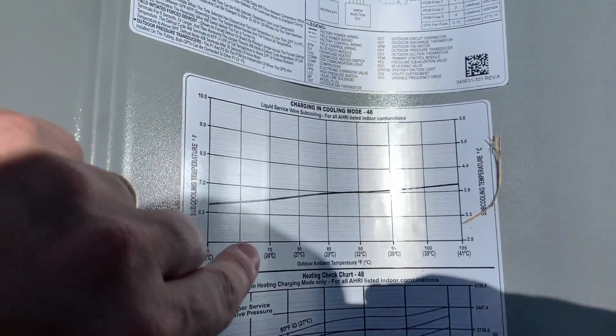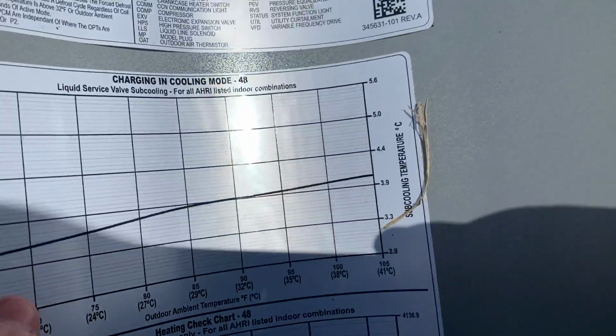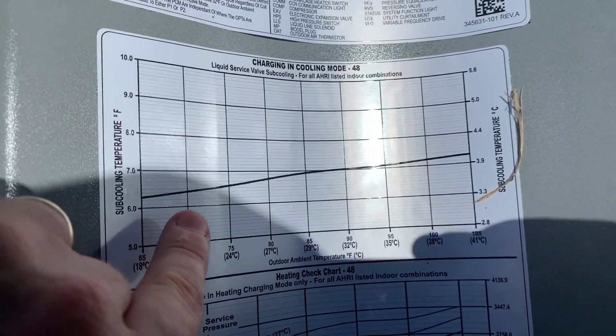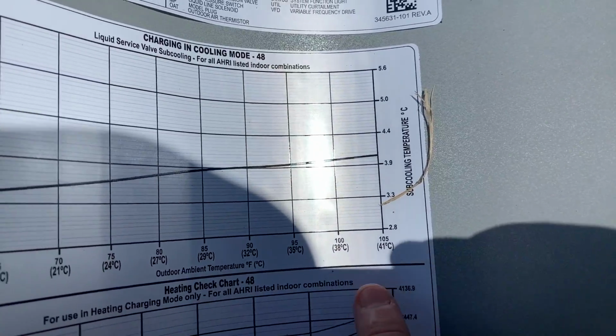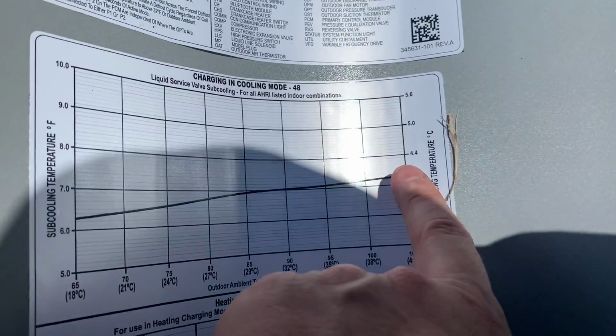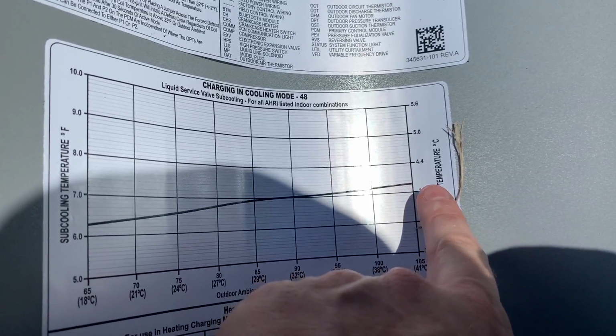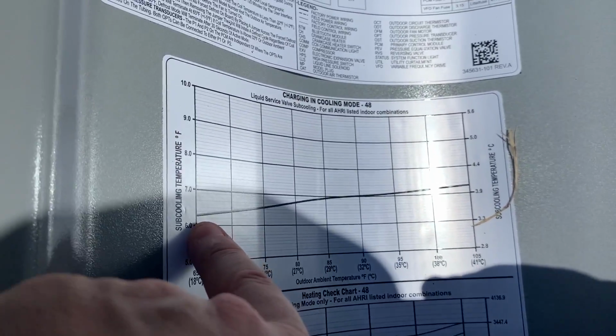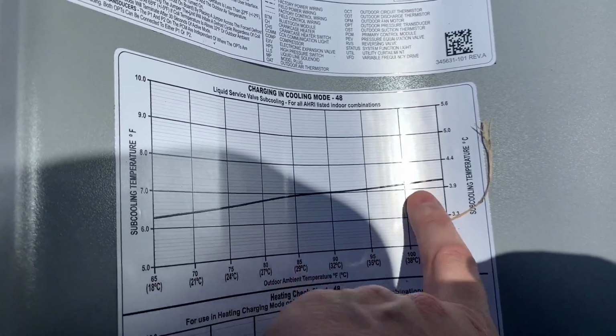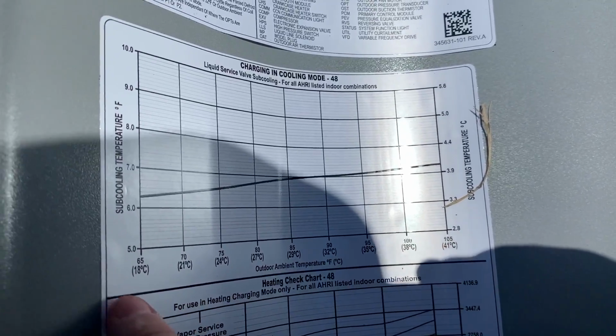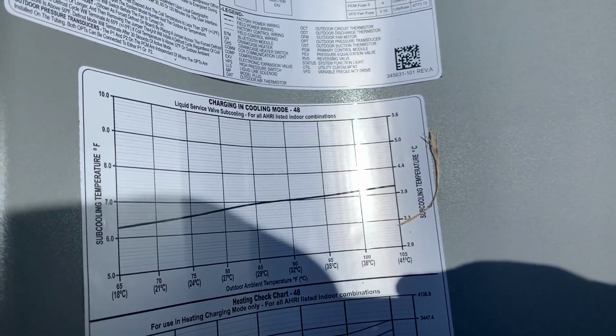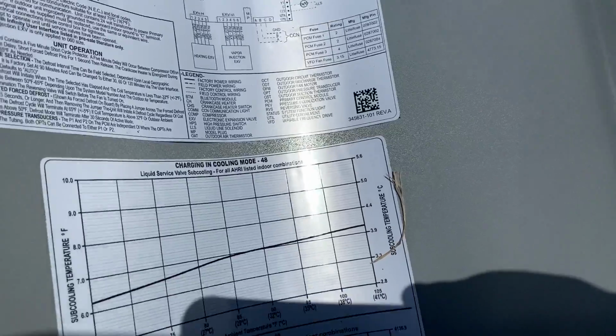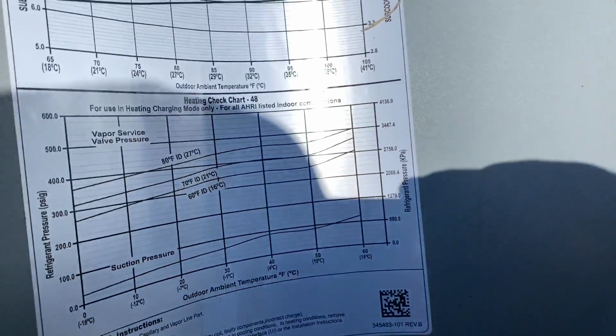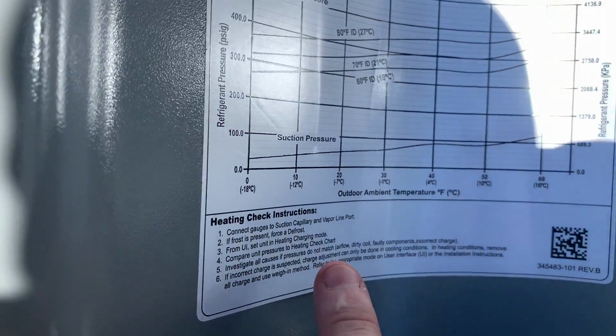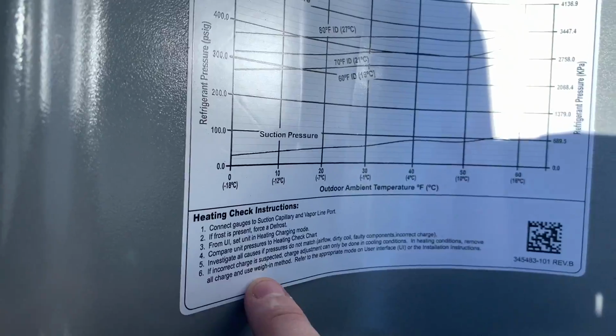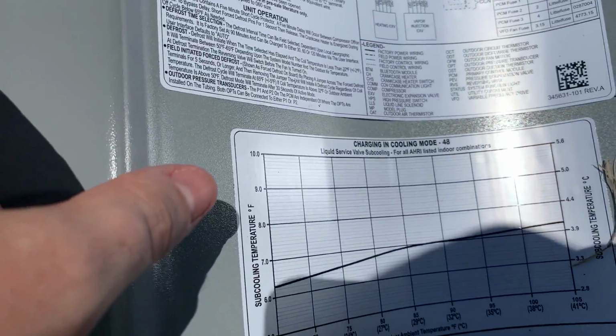One interesting thing with this is it actually has a subcooling curve based on your ambient temperature. So as your ambient temperature goes up, your required subcooling also goes up. I mean, we're not talking anything huge here, starting at like 6.2 and then going up to 7.2, depending on a really wide range from 65 to 105. But that's just how precise they're being with it. And then you have the heating check chart as well. Again, you always read the manual to make sure that you're doing what you're supposed to do when you got a brand new piece of equipment.